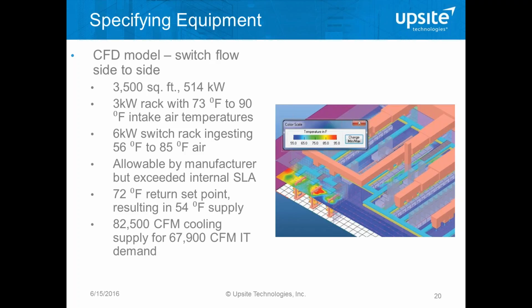While those inlet temperatures were acceptable to the manufacturers, they were not acceptable to the SLAs that were agreed on with the customer here. And just to meet the performance in this data center, we had a 72 degree set point resulting in a 54 degree supply temperature, and we had airflow that was running over 21% in excess of the actual demands of the airflow in this data center.